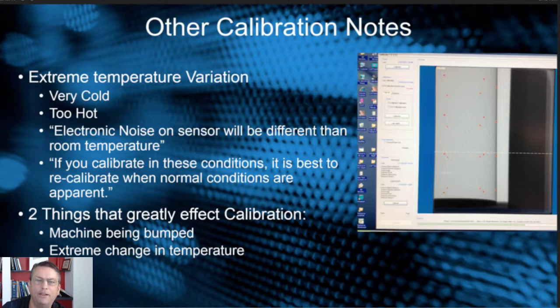The engineers tell me the two things that greatly affect calibration are if the machine is bumped hard, or an extreme change in temperature. If a patient hits your machine, you might want to recalibrate after that.